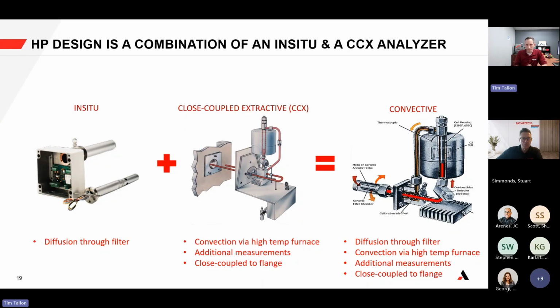But I mentioned that there's this convective loop, right? I mentioned in the close-coupled extractor type that there's this convective loop. There's a very high-temperature furnace. That high-temperature furnace enables the zirconium oxide measurement, but there are other advantages of this convective loop. There's the advantage of additional measurements, like a combustion measurement, like a methane measurement, and also the fact that it's right on the process flange. There's no added sample line, there's no added delay in a measurement. And if it's high particulate already, it's already hard and difficult to measure. So it helps to have it on the process flange.